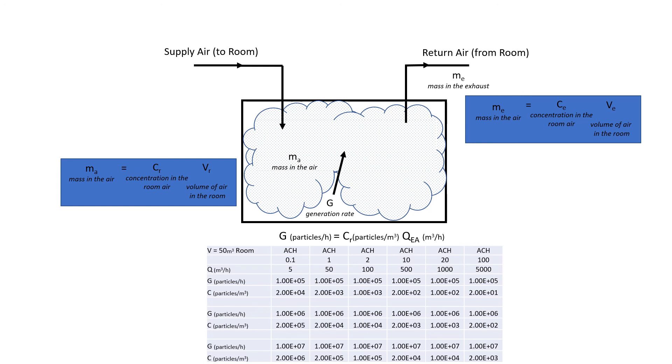And then there's almost no spaces that have 100 air changes, and dilution ventilation would be a very poor tool for that. If you need to remove particles at more than one log or two log, then you would use filters. A HEPA filter is 99.97% effective, and so that's a 4 log reduction going across a HEPA filter. Dilution ventilation kind of pales in ability compared to that.